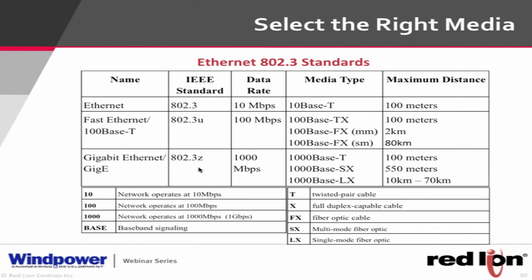So a 100 meg switch is what a lot of people usually get for this type of application, because we're not sending a lot of data. We're just sending a lot of packets per second, but we're not sending really big packets. So we don't need a huge pipe. We don't need to pay a premium for gigabit Ethernet at every one of the ports, because we're not producing a gig of traffic. And so you buy a 100 meg switch with maybe a gig backbone. So your ring may be a gig, but the individual ports that connect to the end devices will be 100 meg.